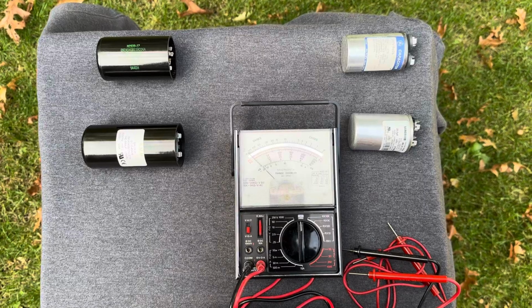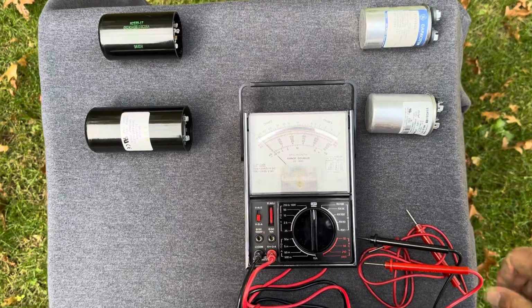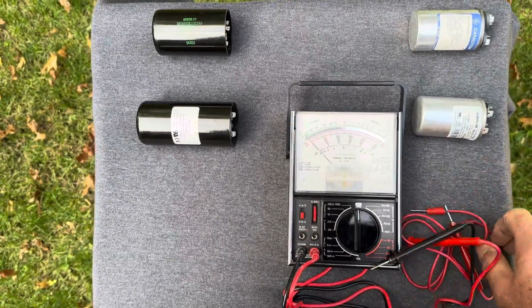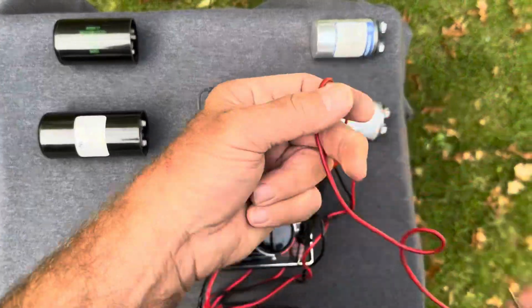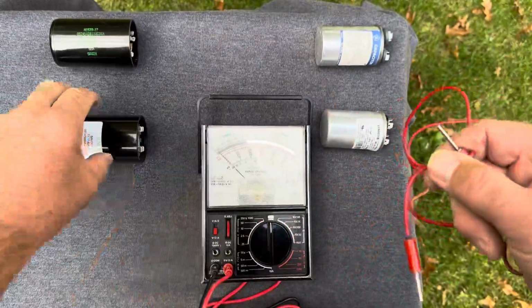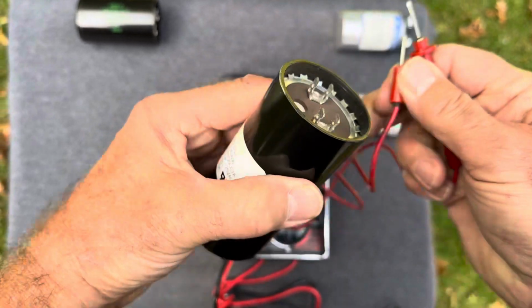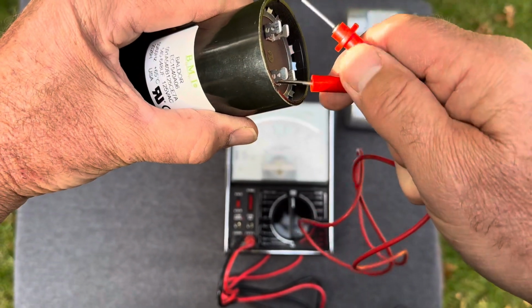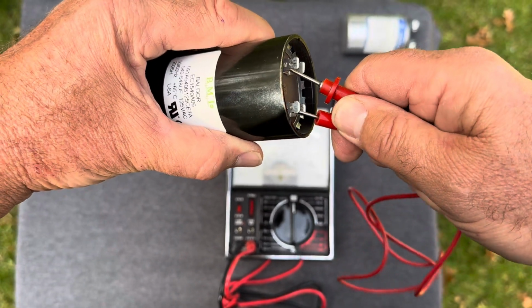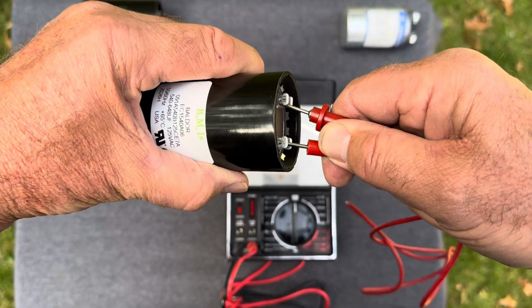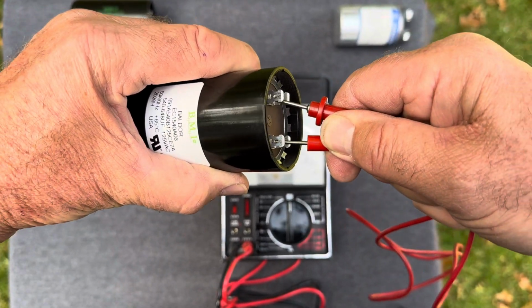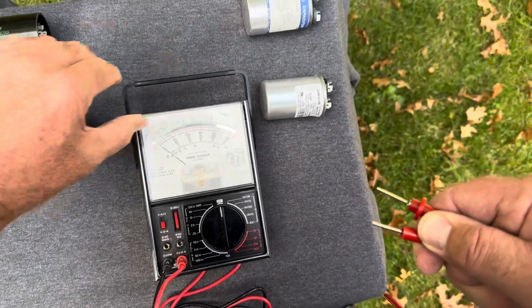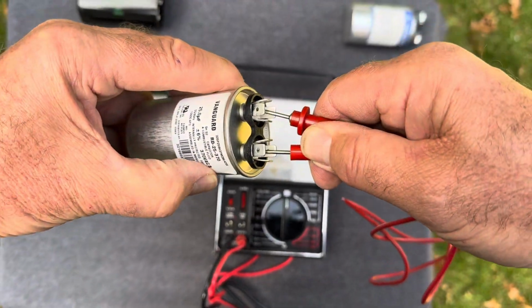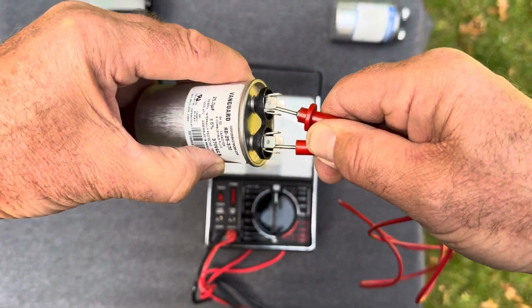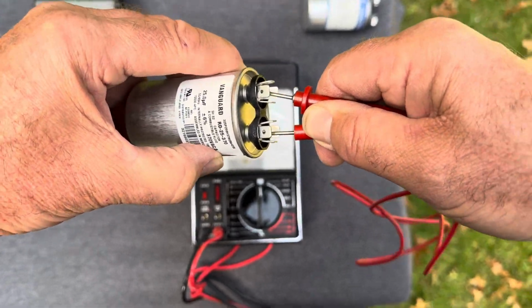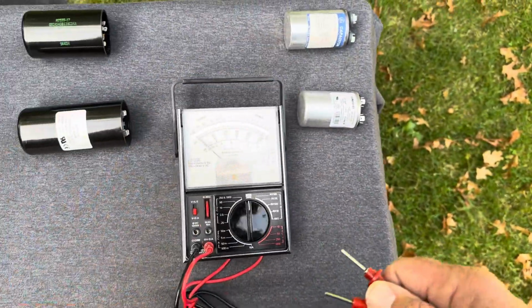But make sure that before you do any testing you discharge them. Take a piece of wire or a probe and touch it to the two terminals. Avoid touching the terminals with your fingers until you discharge them - it's pretty easy to do, just touch them together. That takes any voltage out of there that might be in there, shorts it out.